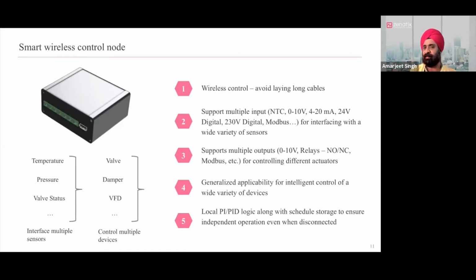You could connect any sensor and program the linear coefficients for converting the 0 to 10 volt or the 4 to 20 milliamp signal into, let's say, the CO2 value, right? All those things are completely configurable over the cloud, which means, let's say you are only using 2 analog channels and one of those channels goes bad, right? For a regular DDC, you would have to change the programming. Here, you simply shift the sensor from one analog input channel to one of the unused analog input channels, and you just configure it from the cloud, and that's it. You don't need to reprogram it in the field, right?